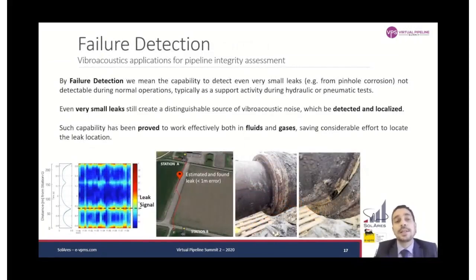Failure detection is another technique that we use with the same vibroacoustic technology to detect and localize very small holes, typically caused by corrosion. In this case, you typically already know there is a hole, but you don't know where. So we assist in hydraulic or pneumatic tests, and we are able to detect a very, very small signal coming from a tiny pinhole corrosion point.